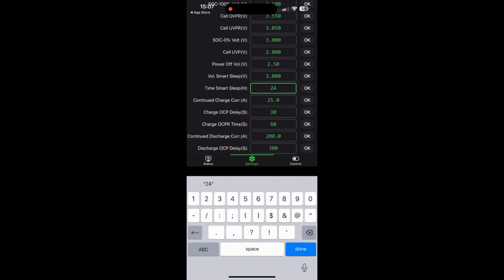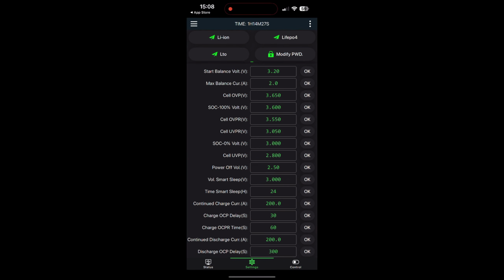So to explain it, if the battery bank goes to 3 volts, it has 0 current going in or out, and it's in that state for 24 hours, the BMS will then turn off. Okay, next one, continue charge current. What this basically is, how much charge current do you want to allow to be going into the BMS or into the battery bank. These are rated for, say, 200 amps, so I'm happy to put it at 200 amps, but for example, most cells like to be charged at 0.05 C.